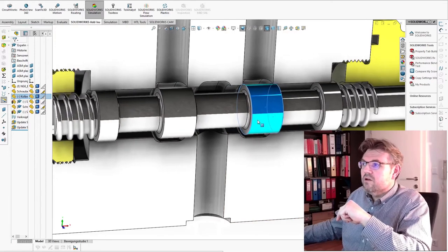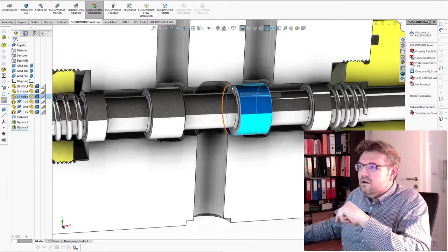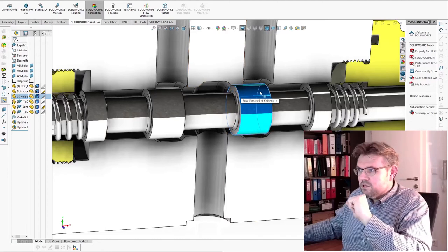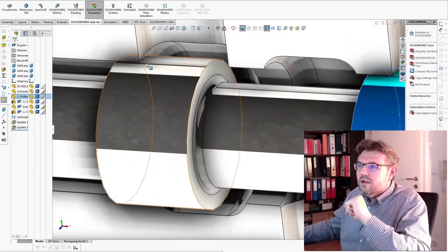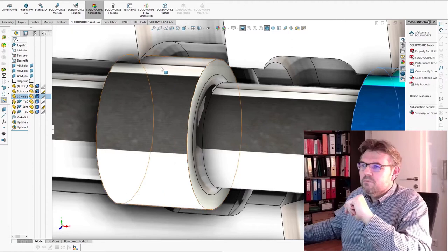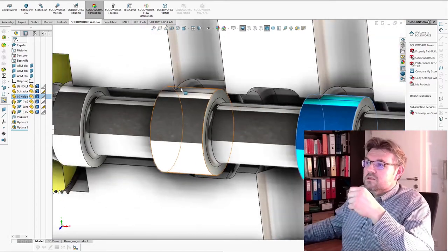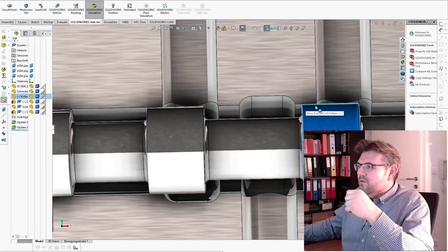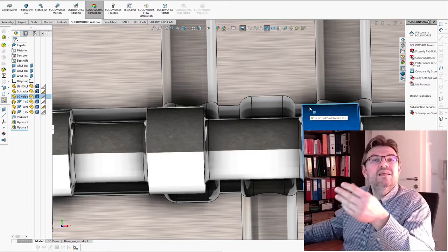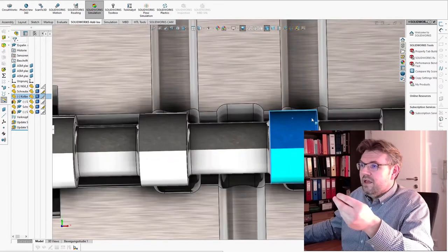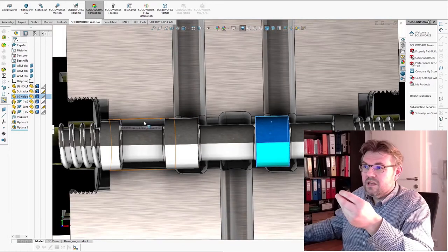And now you can imagine if here is some dirt or something like this, if we rub this dirt, we will make scratches in the surface. And if there are scratches, there is quite some oil passing. There is anyway a gap between the hole and the piston. There is a gap simply because it needs to be lubricated. So there will always be oil running between the walls and the piston. There will oil rush through. This is the leakage. We always have leakage. And on this side, if here is the pressure, the leakage will always appear here. So we'll also have leakage here.